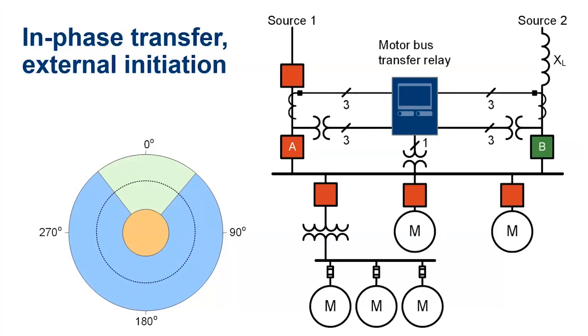For the in-phase transfer, we need to take into account the breaker close time. And the reason for that is that, say, there is a fault on source one, and that will slow down all the motors and will bring the voltage down. And after the bus is isolated from the fault, all the motors start recovering, the residual voltage recovers a bit, and then we have to deal with larger slip frequencies between the bus and the other feeder. In these cases, we get the signal to start the transfer, so we send the signal to open our breaker to isolate the bus.